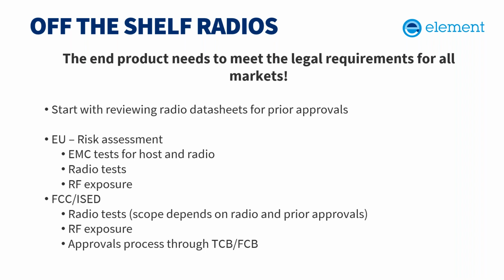Another note is if you're buying an off-the-shelf product like a laptop and incorporating it into your medical device system without making any changes to the radio, no additional radio testing should be required for the laptop, but you still need to gather the required information for the EU and include it as part of your certification.